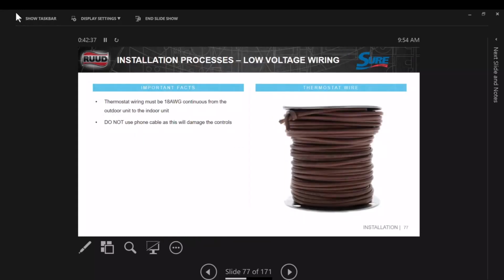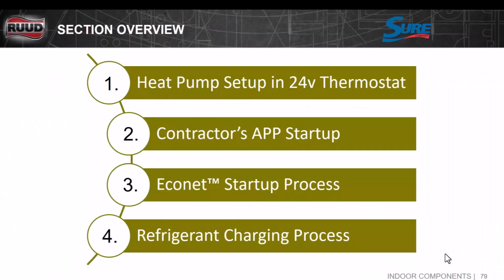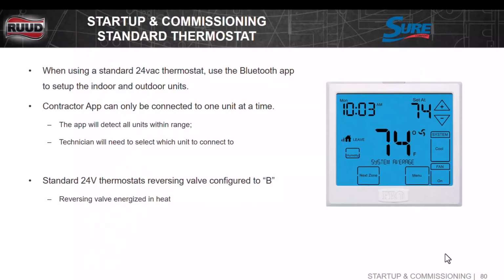So thermostat wire, as we talked about a while ago, 18 gauge solid thermostat wire. So to start up, we just got to go through and make sure everything's set up properly. Here's the heat pump setting here. So this is a heat pump with a regular 24-volt thermostat, regular thermostat wires, all that. The app can be connected to this unit to set up all the things like airflow, time delays, airflow delays, and different CFMs on the unit. Now we use the B terminal because we energize in the heat mode on our heat pump. So keep that in mind too.